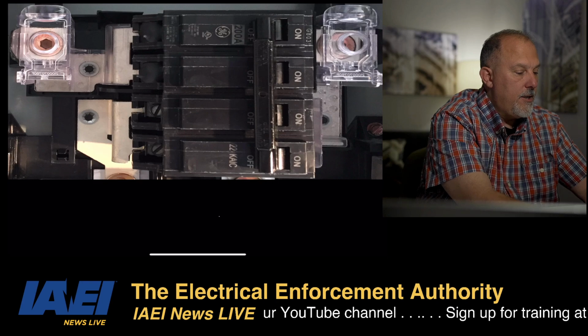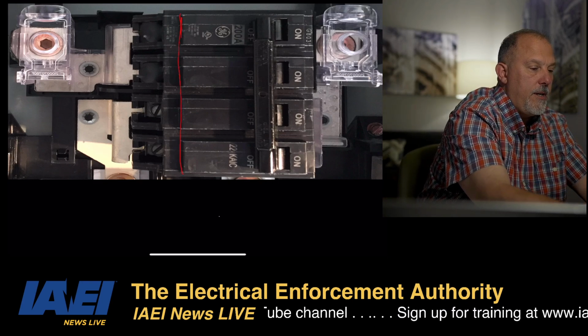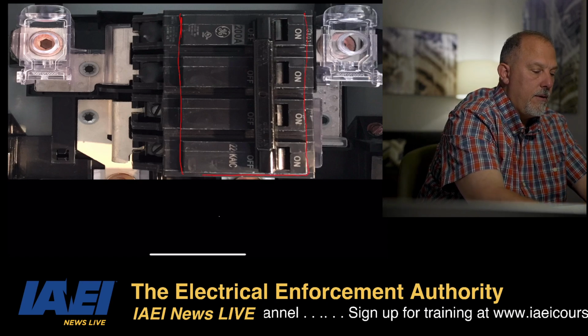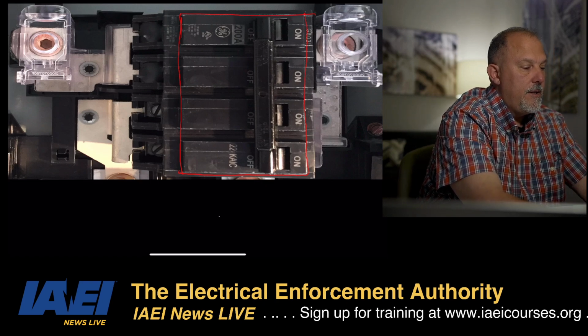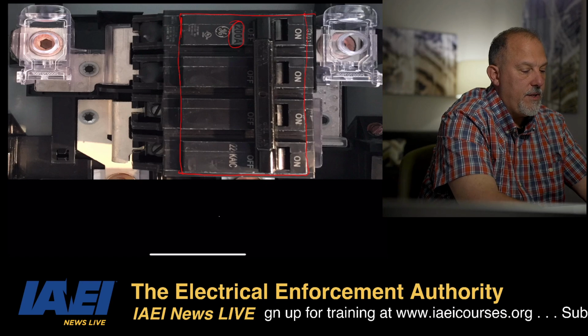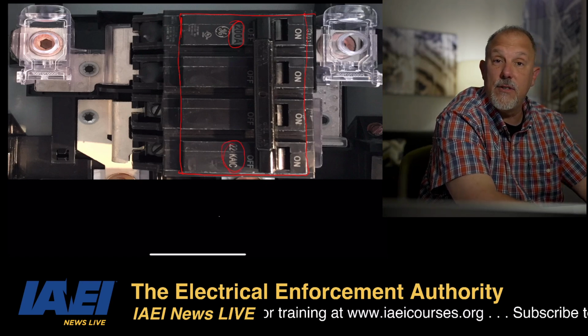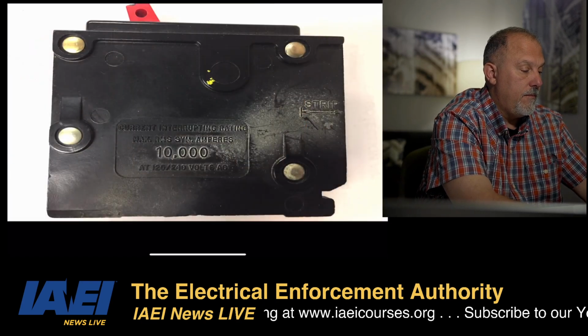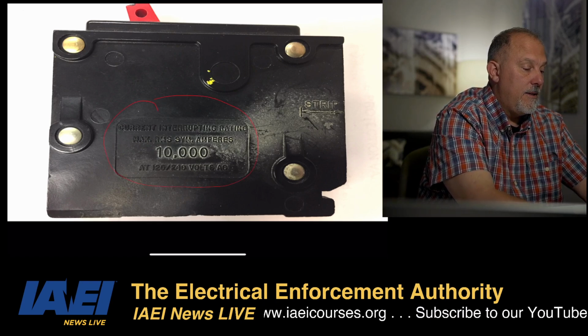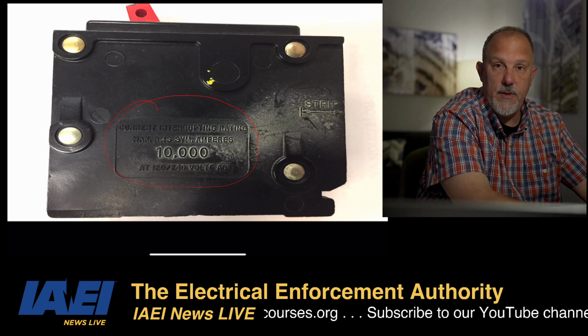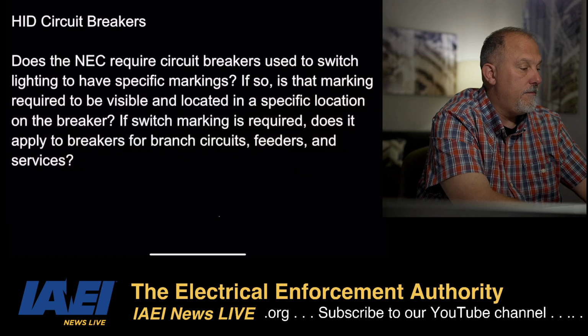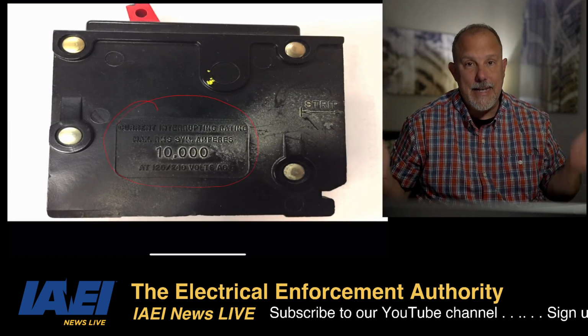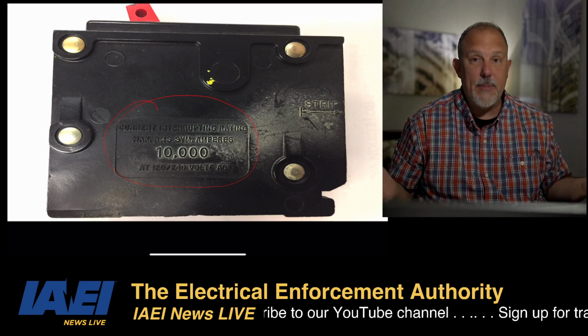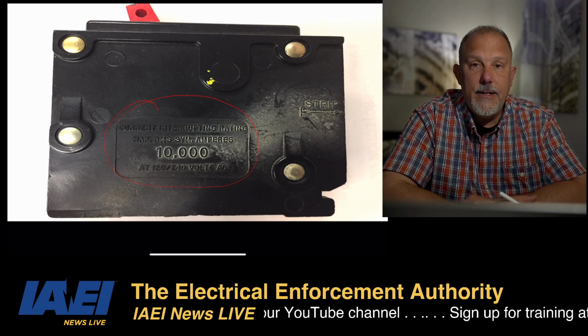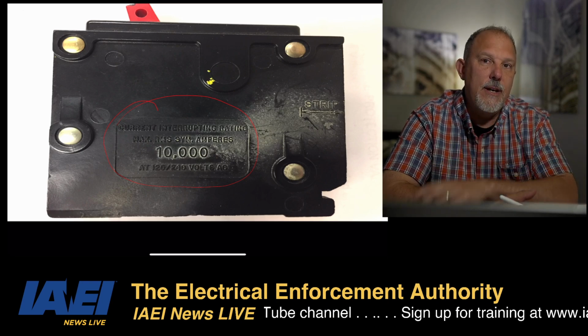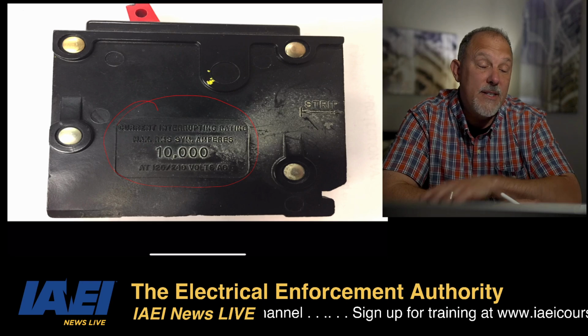Now this one here, so you can see where the dead front goes. The dead front would go here and here. So you have the ampere rating, which is visible, and there's your 22K AIC. So this is a 22K GE breaker. This one is on the side. Now you would have to actually remove this circuit breaker to find its interrupting rating. So answer, yes, it's required to be marked. Where? It depends on the rating and a couple of those areas, so take a look. You can always rewind and pause this video.